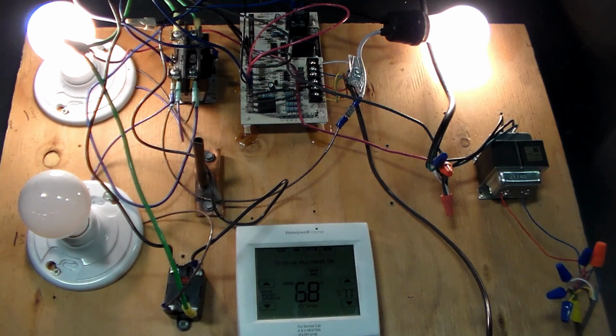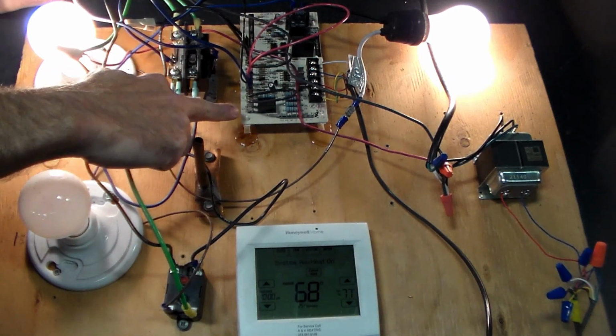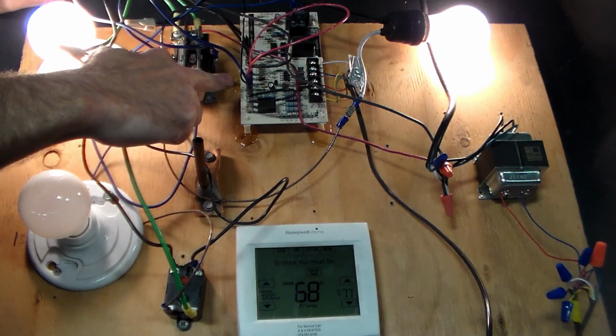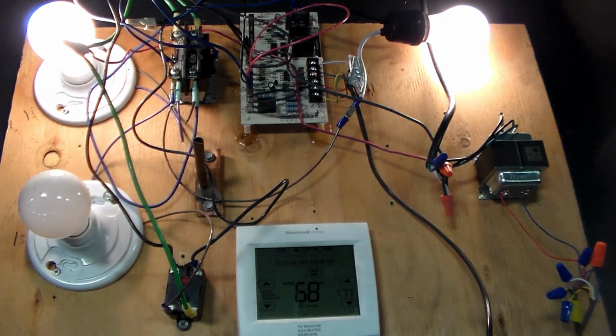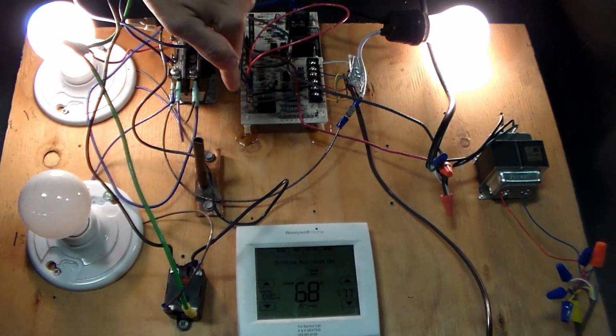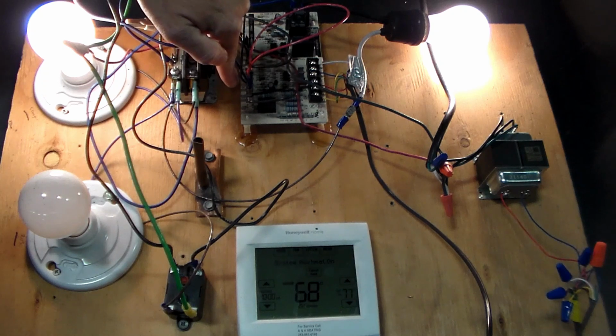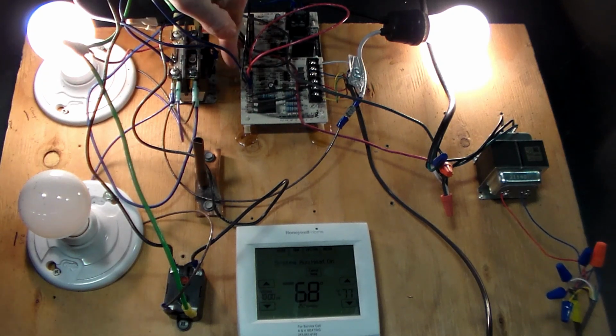That doesn't necessarily mean there's not other things wrong with the board, but the board itself is doing what it's supposed to do. So now we can look at some of these external components, like the high pressure switch, or the defrost sensor itself, or the low pressure switch, or maybe the reversing valve, or whatever might be the cause. But we have to first start by understanding what these terminals mean on here, and that's 80% of the battle probably. Understanding your stat wires: what is Y, what is O, what is R, common, what is the function of W1 or W2 or D if it's a Rheem, and then over here how this is wired with the high pressure sensor, the contactors, your Ys, DF is your defrost sensor, low is your low pressure sensor, and then O out goes to your reversing valve.